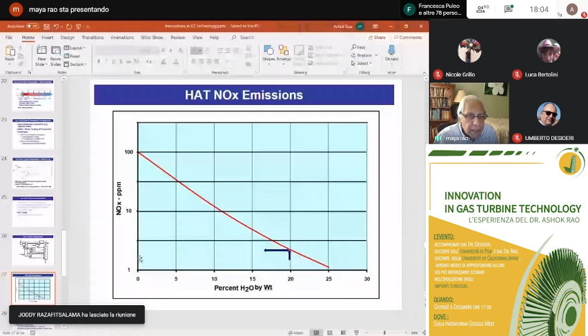Now, another advantage with this cycle is that there's no steam bottoming cycle, the Rankine cycle. So that leads to a significant amount of capital reduction. And various studies have been done comparing the efficiency of this HAT cycle to other gas turbine based cycles, and they have found improvement in efficiency over the combined cycle. One big advantage is the essentially flat heat rate, or efficiency, down to 60% load.